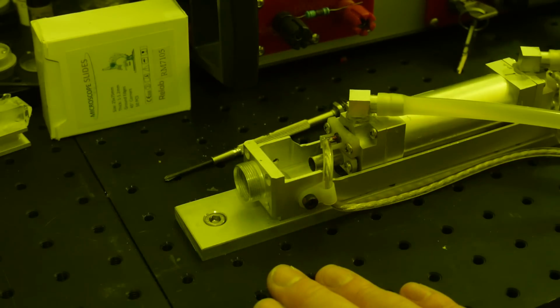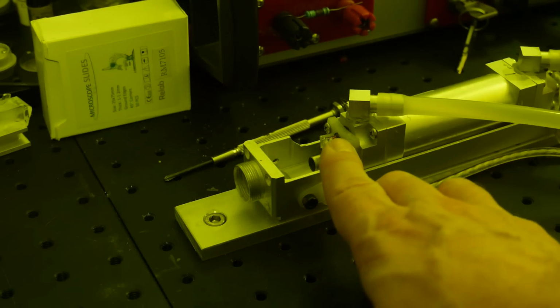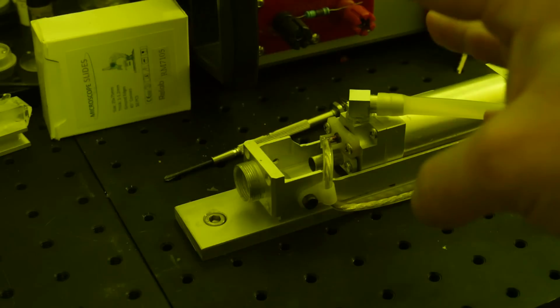So there is still a very serious fault with this power supply. What we've got here is a view of the end of the head, and we can see the end of the flash lamp just poking out there. What should happen is when this laser fires, we should get a single bright flash out of the end of the quartz envelope for the flash lamp, and that should be it.